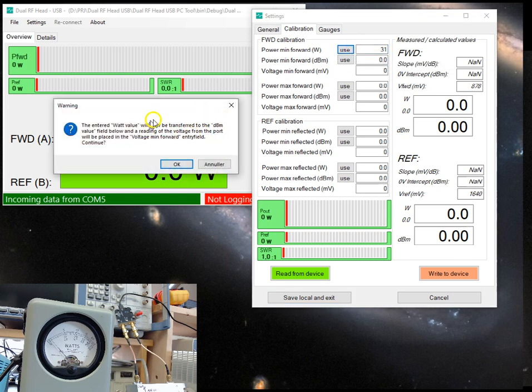When I do that, I get a warning. It says the entered watt value will now be transferred to the dBm value field below, and a reading of the voltage from the port will be placed in the voltage minimum forward enter field. Continue. What it tells me is that it will convert the 31 watts to dBm, and it will read the analog voltage and put it in this enter field.